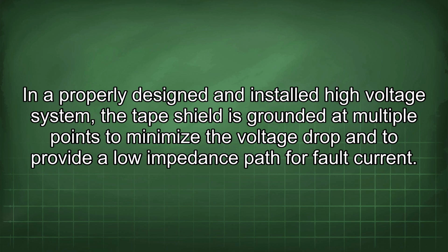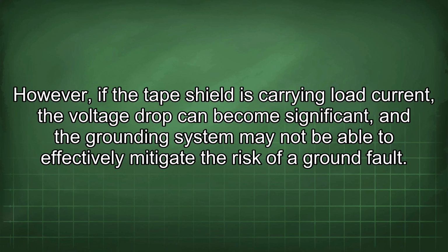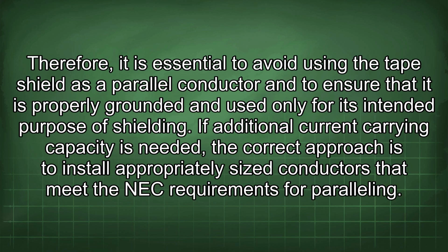In a properly designed and installed high-voltage system, the tape shield is grounded at multiple points to minimize the voltage drop and to provide a low impedance path for fault current. However, if the tape shield is carrying load current, the voltage drop can become significant, and the grounding system may not be able to effectively mitigate the risk of a ground fault. Therefore, it is essential to avoid using the tape shield as a parallel conductor and to ensure that it is properly grounded and used only for its intended purpose of shielding.